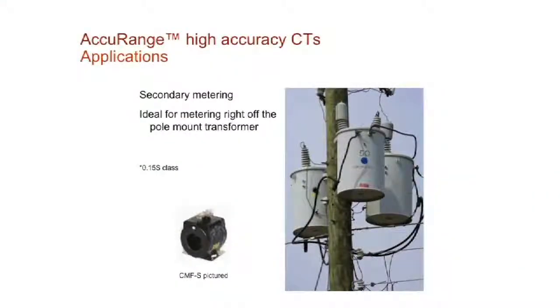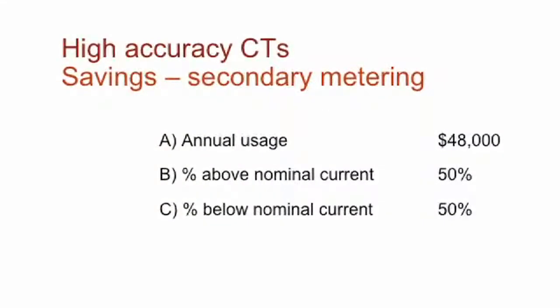We also have what's called the CMFS. Typically you'll see these either up near a distribution transformer or when the distribution transformer is going directly into an installation. You'll see these hanging on the wires in an outdoor environment and then connected to a meter as the electricity goes into a building. If you drive around lots of cities, you'll see these if you just kind of take a look up. So let's talk about the savings that you can find at the secondary metering level.